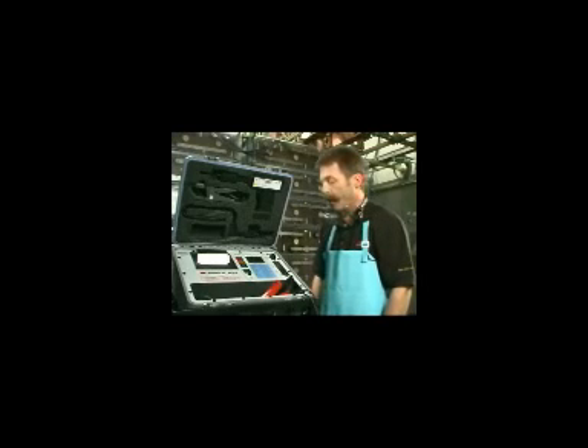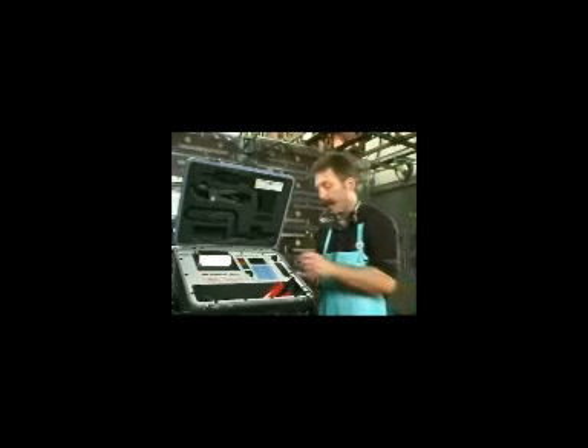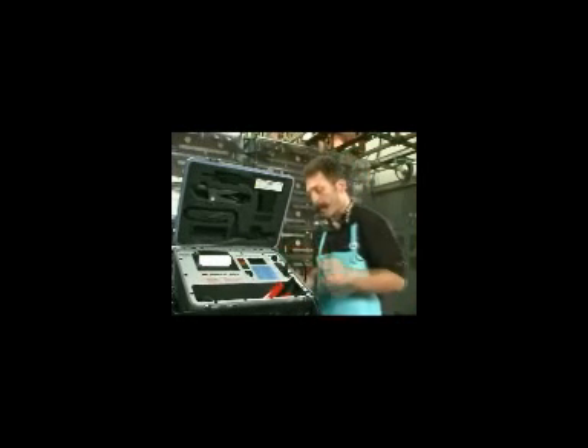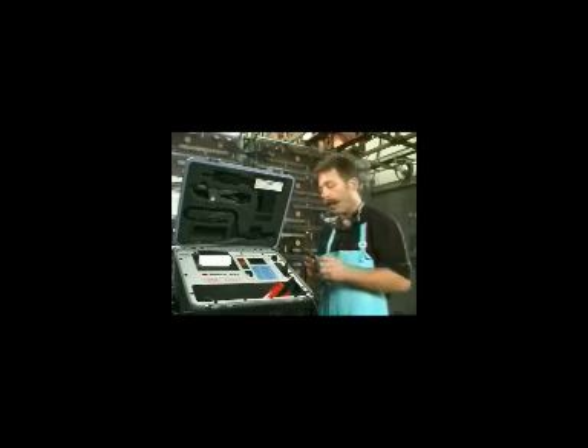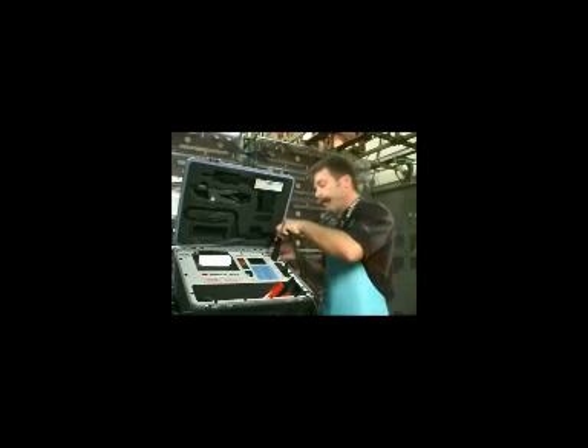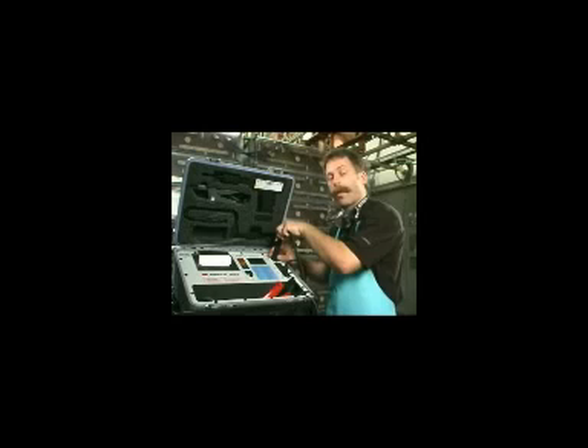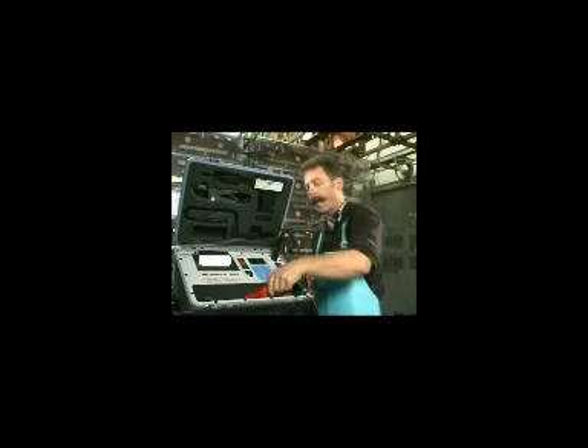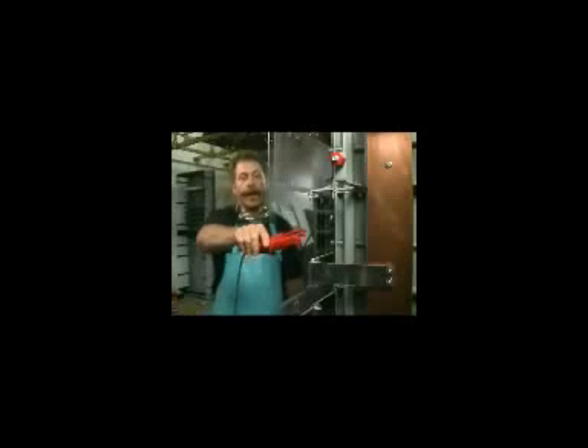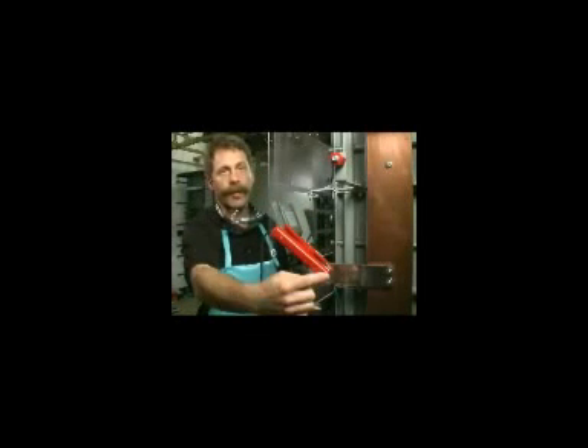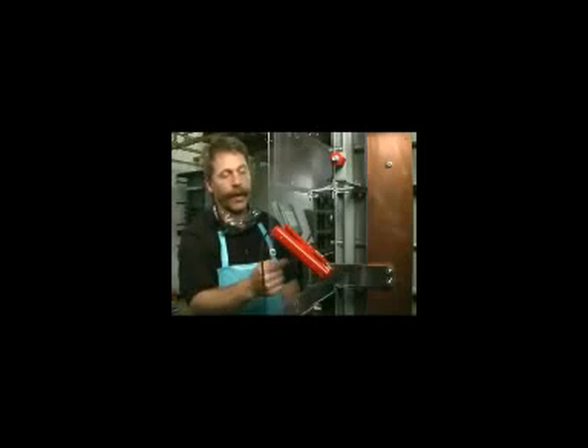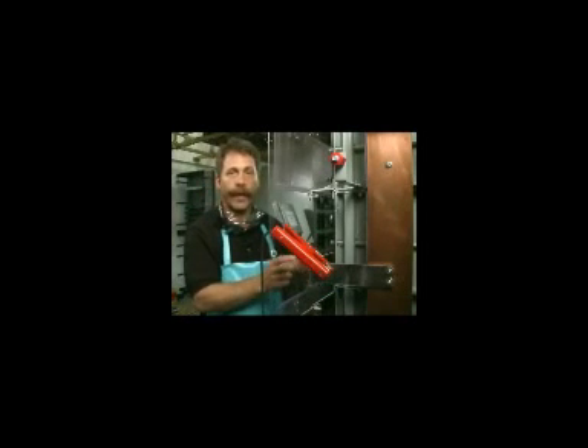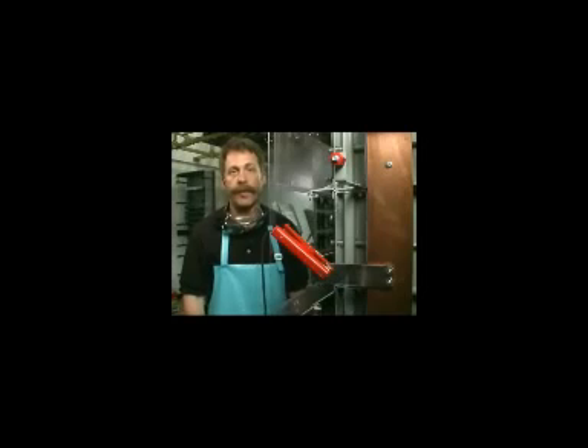The connections we make will be the 110 power connection to the input module and the current source leads, which are keyed and actually apply the current to the battery. We take the red lead and apply it to the positive bus. Now we're going to make our connections to the positive bus bar outside the cell. You can see the copper bus bar with the connection to it, and this red lead is outside the cell. That way we get proper current density when taking the measurements for the impedance.